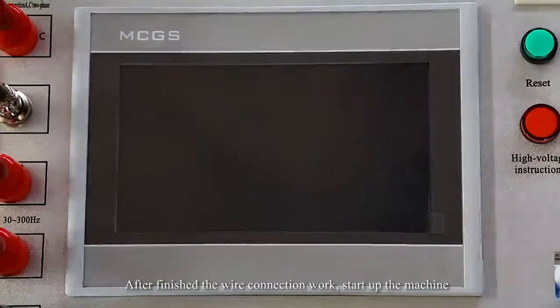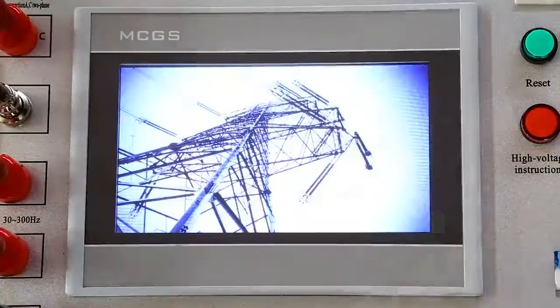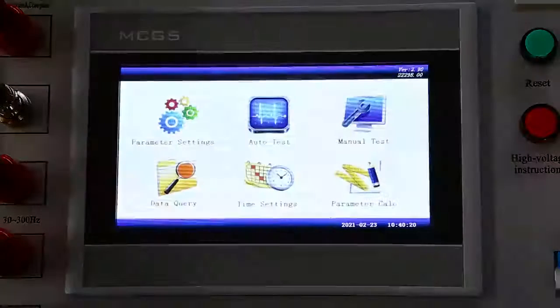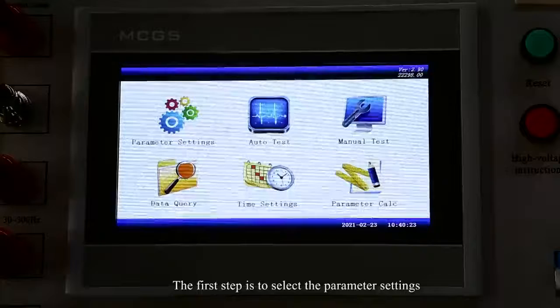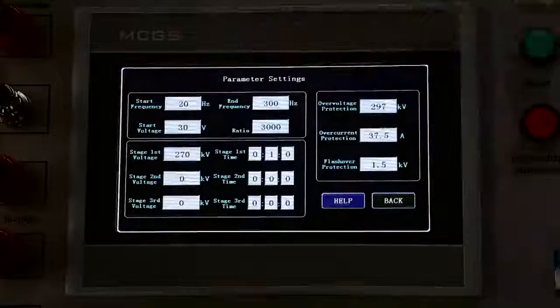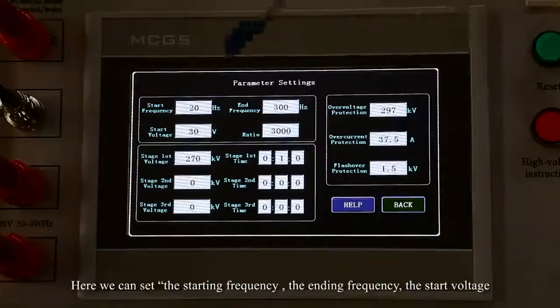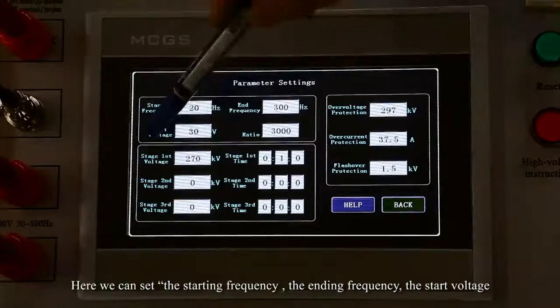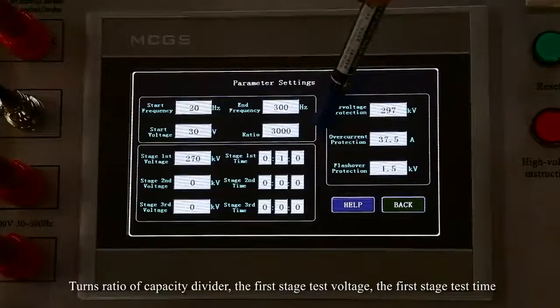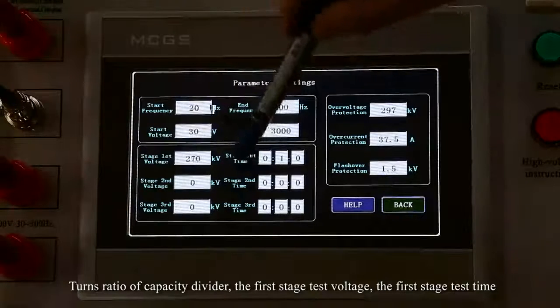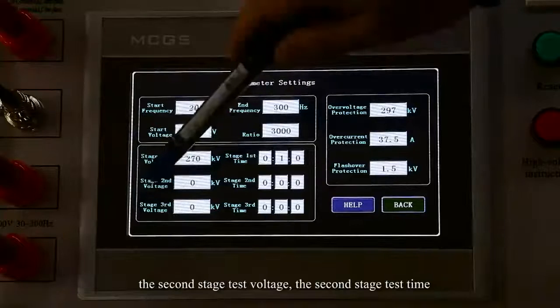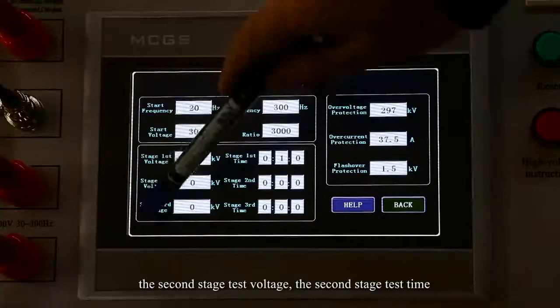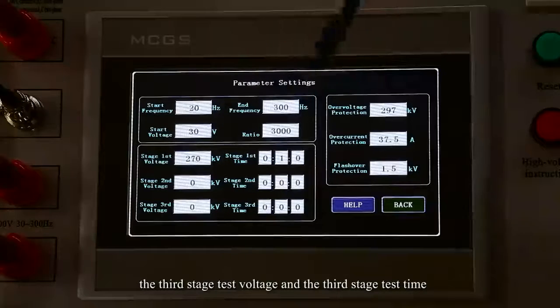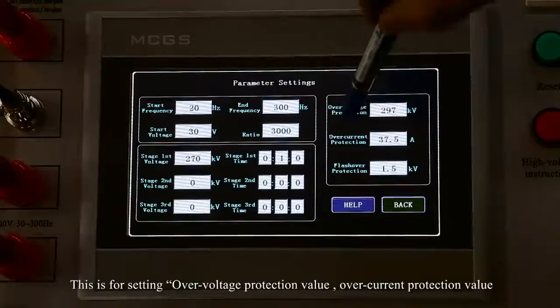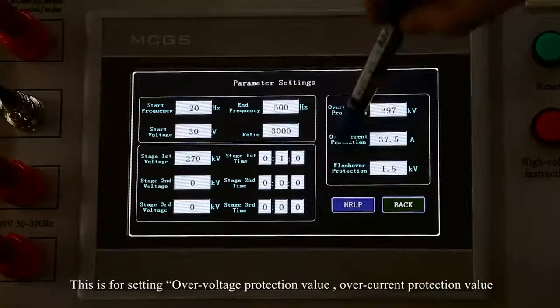After finishing the wire connection work, start up the machine. The first step is to select the parameter settings. Here we can set the starting frequency, the ending frequency, the start voltage, the test ratio of the capacity divider, the first stage test voltage and test time, the second stage test voltage and test time, and the third stage test voltage and test time. This is for setting the overvoltage protection value, the overcurrent protection value, and this is the flashover protection value.